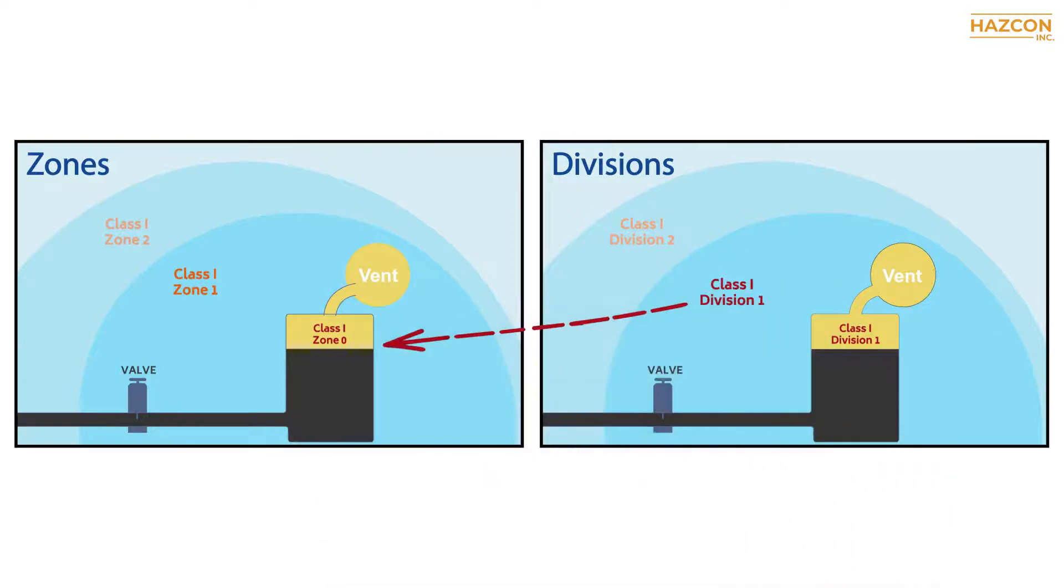Class 1 Division 1 products are permitted to be installed in zone 0. Please note that only intrinsically safe products, EX IA may be installed in zone 0. Class 1 Division 1 products may be installed in zone 1 and in zone 2 and may also be installed in class 1 Division 2.